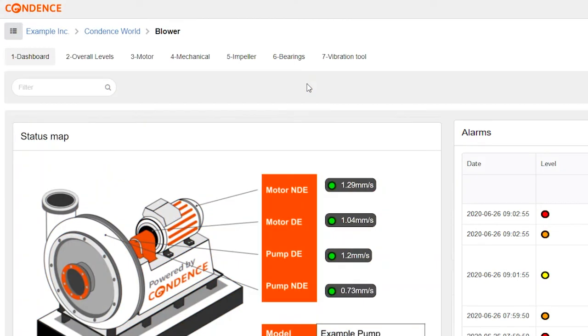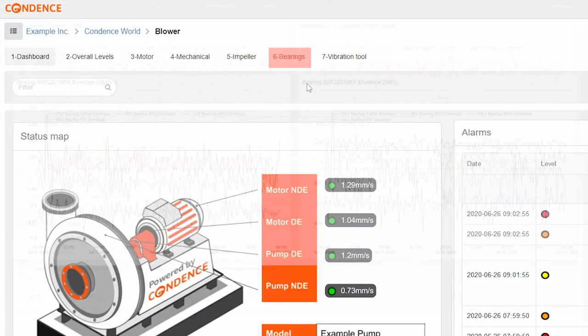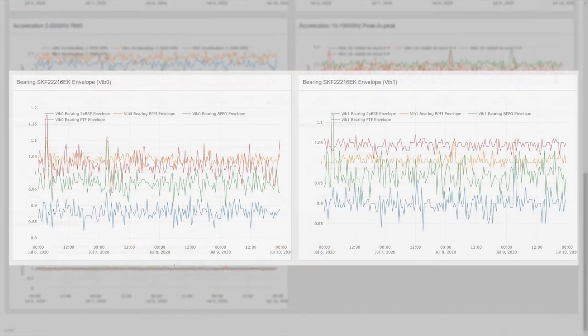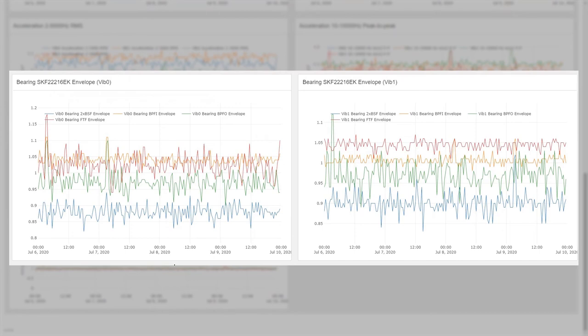And last but not least, the bearings. We've added the trends of the asset's bearings. We've selected the envelope metrics for the dashboard as the failures usually begin to be visible first in these. In one component, you can monitor the full selection of the bearings' failure frequencies.